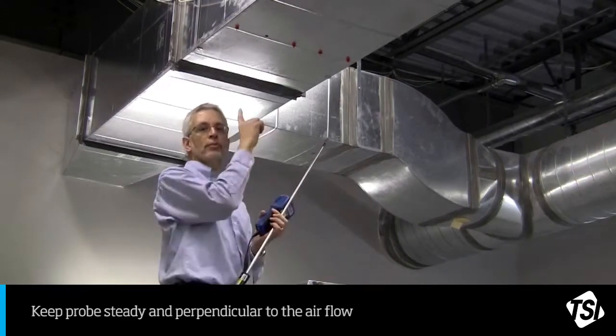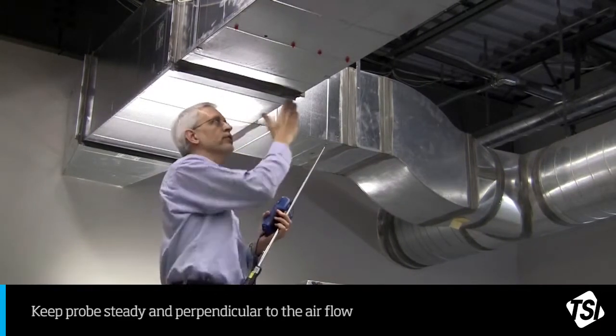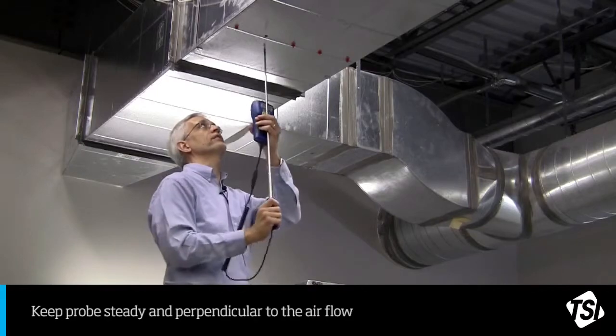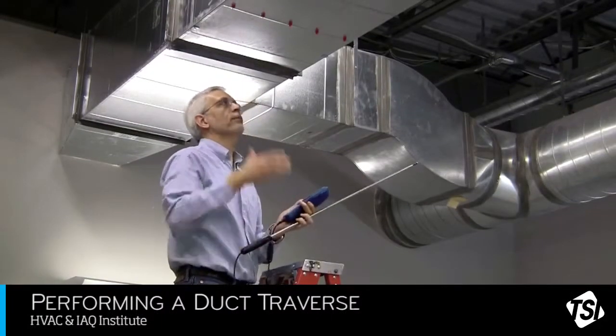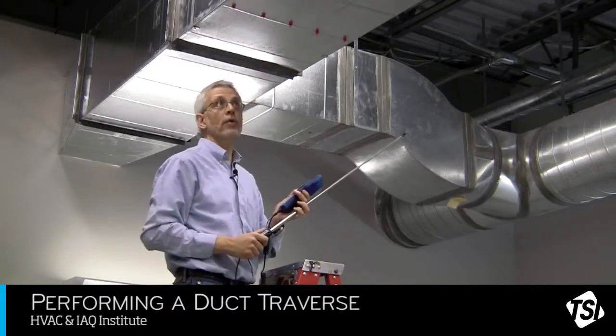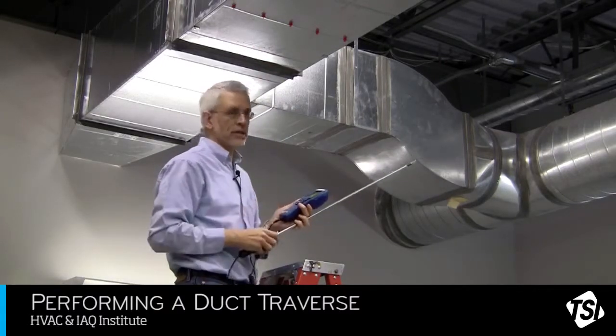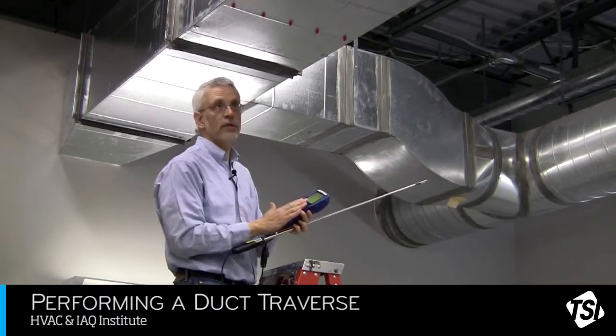I'll take the same measurement locations at hole number 2 and then proceed across the ductwork in the same fashion. I now have 25 readings that represent the entire flow pattern within the duct. We can now look at the statistics that are stored within the instrument.